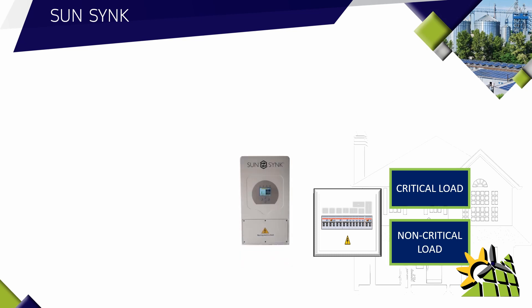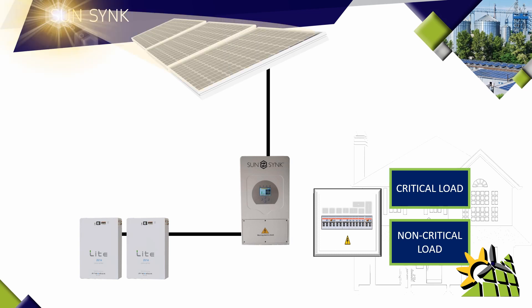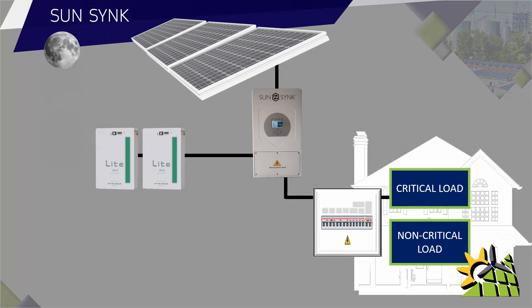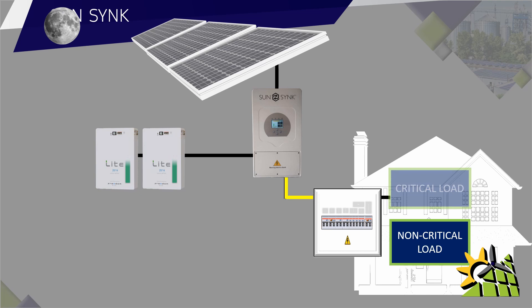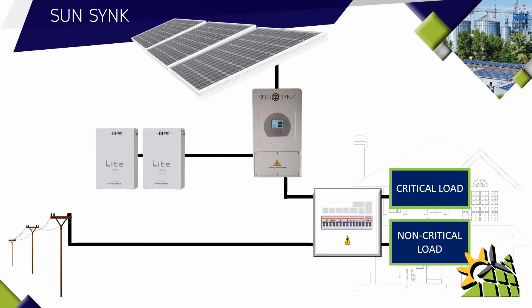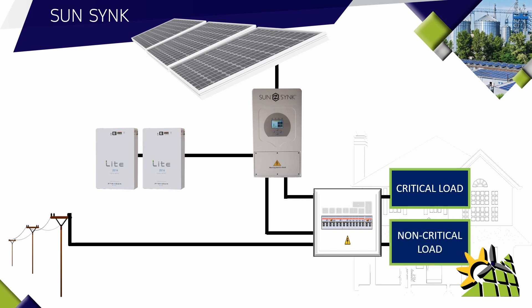A Sunsynk inverter operates with solar panels and batteries. The Sunsynk inverter has a built-in charge controller, so the panels will be directly connected to the inverter, which will then be connected to the batteries. The first priority for the solar panels is to provide charge to the batteries independent from the grid. The output of the inverter will be connected to the critical load, so at night the batteries will provide power to the critical load. If the system is correctly sized, you should have enough solar panels to provide power to the non-critical load, the batteries, and the critical load.